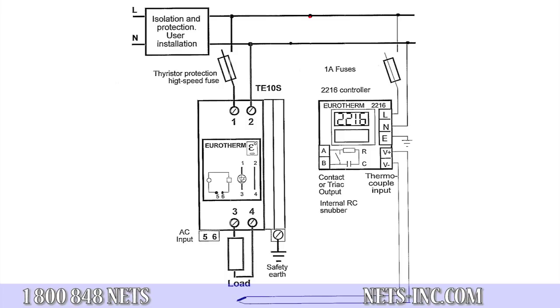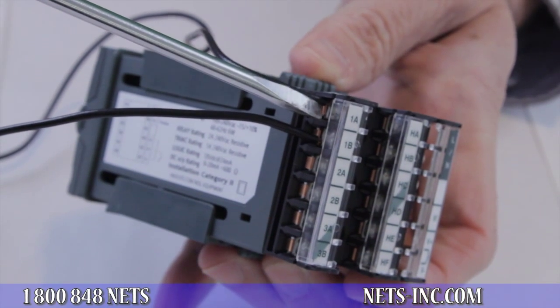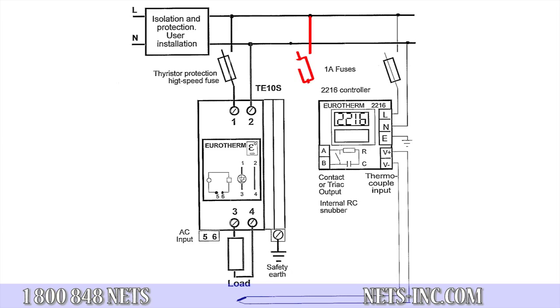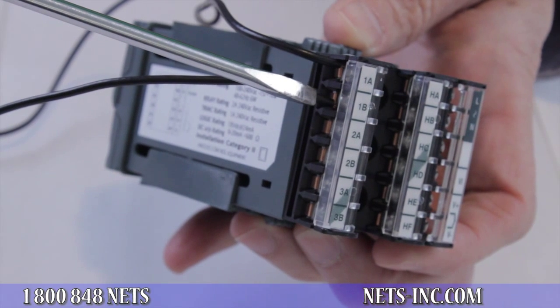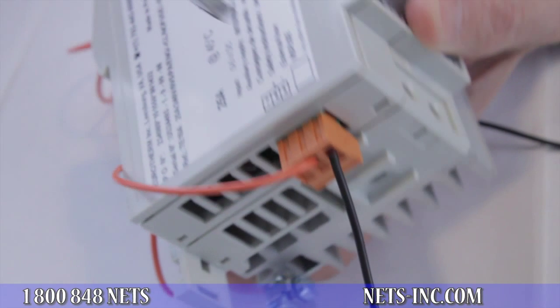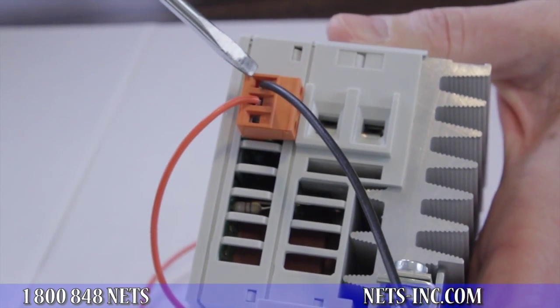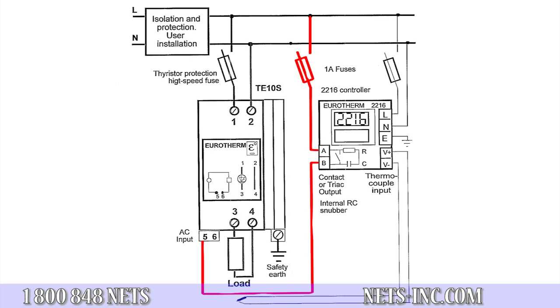In the wiring diagram shown, we are using a Eurotherm 2216E temperature controller and a Eurotherm TE10S power controller with an AC input command signal. First, wire your line voltage to terminal 1A of the temperature controller. Next, terminal 1B is the switched line voltage signal through either the relay contact or triac in the temperature controller. This wire from terminal 1B will be wired to the positive side of the input command on the power controller, which is terminal 5 in this example.